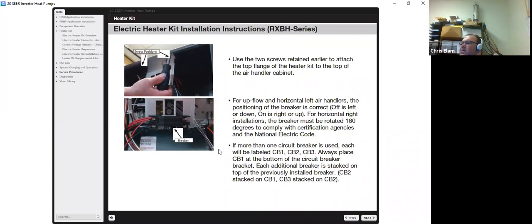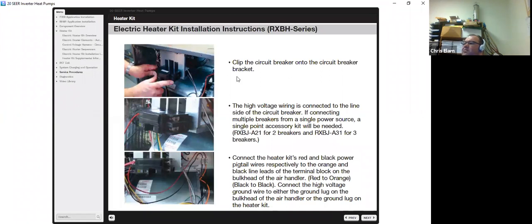Here, for upflows and horizontal left, the position of the breaker is correct. Off is left or down, on is right or up. For horizontal right installations, the breaker must be rotated 180 degrees to comply with the NEC code. If one or more circuit breakers are used, each will be labeled CB1, CB2, CB3. Always place CB1 at the bottom of the breaker bracket. Each additional breaker is stacked on top of the previously installed breaker. Put the breaker back into the circuit panel.